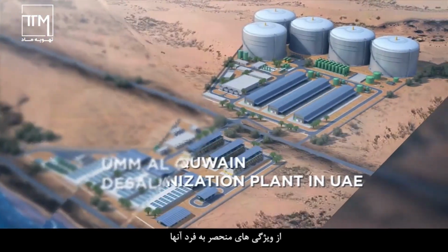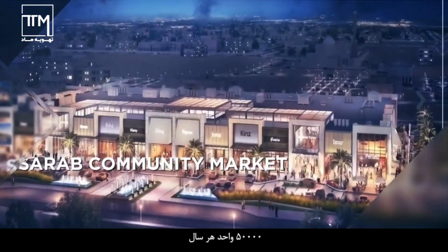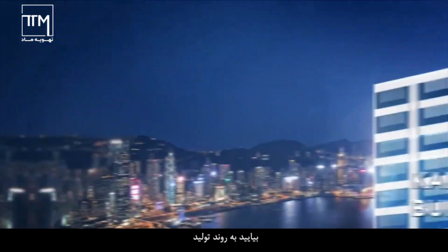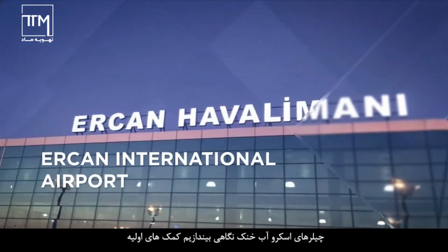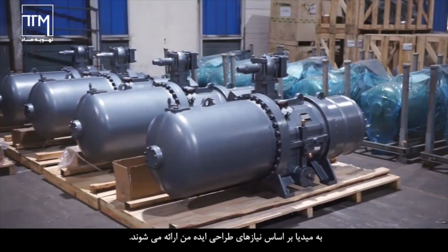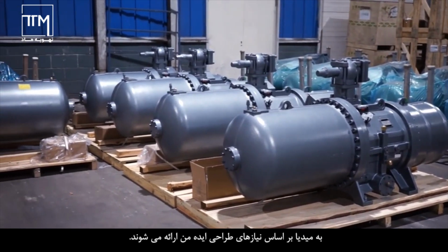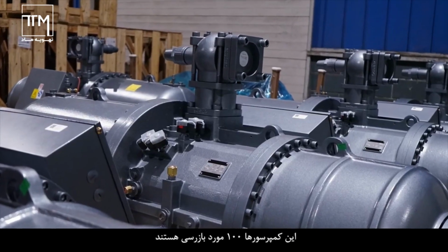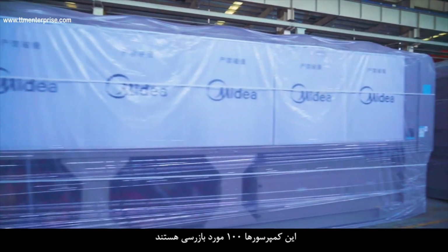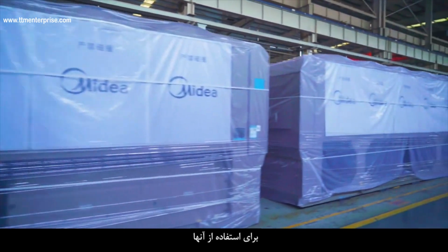Screw chillers are widely used because of their unique characteristics. The global market volume of screw chillers is over 50,000 units every year. Let's look around the production process of water-cooled screw chillers first. Here's the inventory area of screw compressors. These compressors are specifically supplied to Midea based on Midea design requirements. These compressors are 100% inspected before they are used.